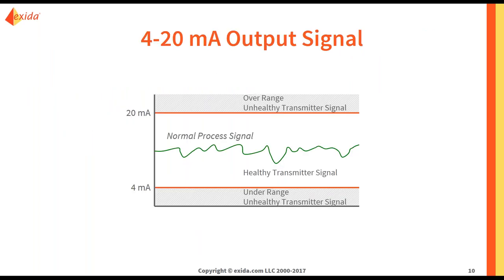As long as you are in that range of 4 to 20, you have a healthy signal. However, if you are over range or under range, you have an unhealthy transmitter signal which often indicates a failure. I am going to go through the different ways that your transmitter might fail internally and what that might look like.